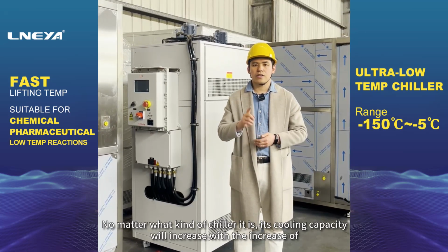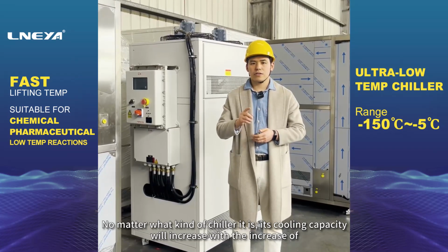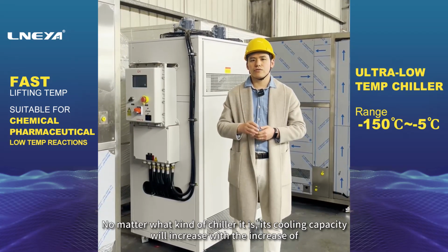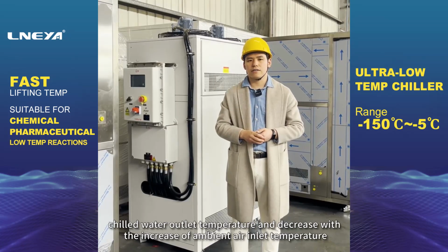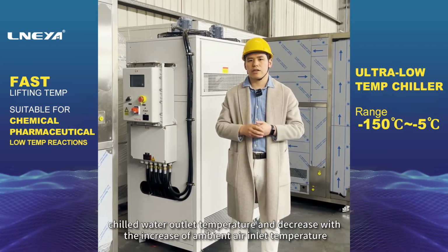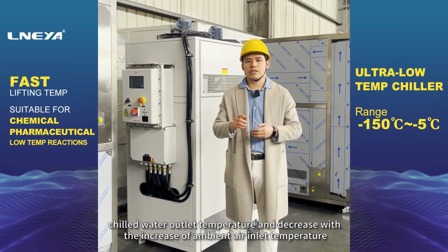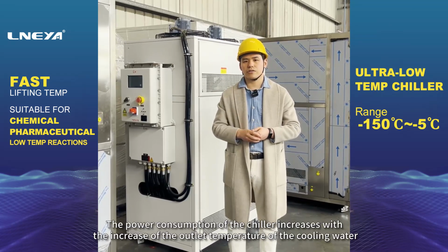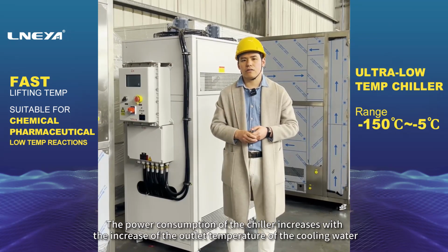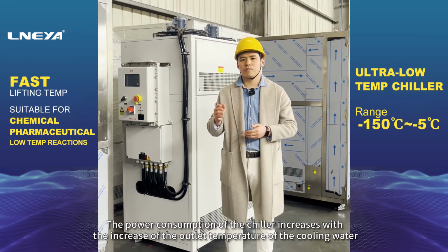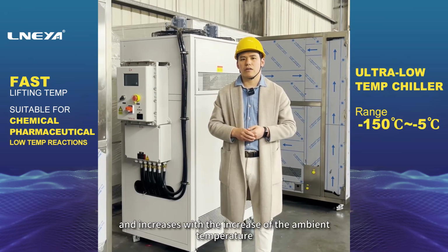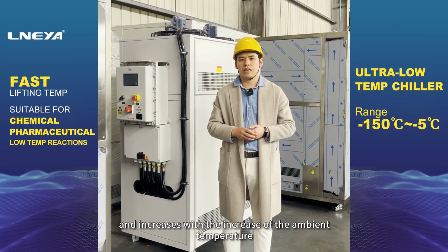No matter what kind of chiller it is, its cooling capacity will increase with the increase of chilled water outlet temperature and decrease with the increase of ambient air inlet temperature. The power consumption of the chiller increases with the increase of the outlet temperature of the cooling water, and increases with the increase of the ambient temperature.